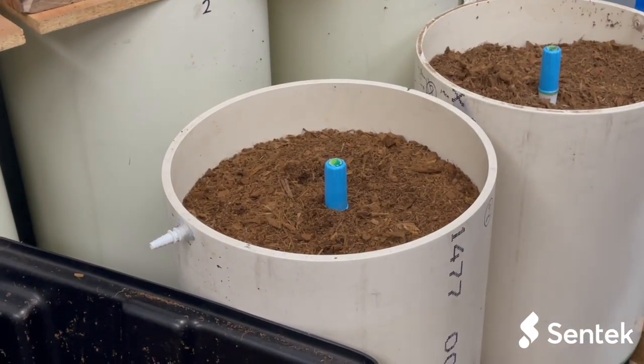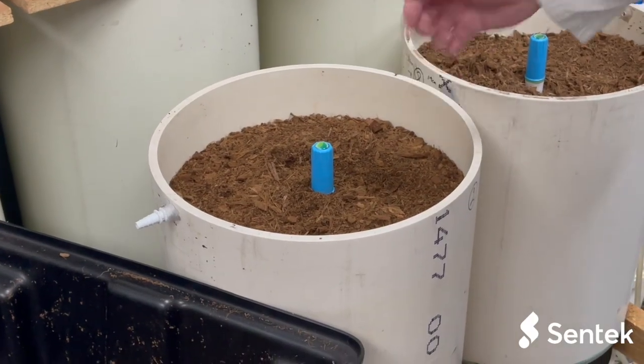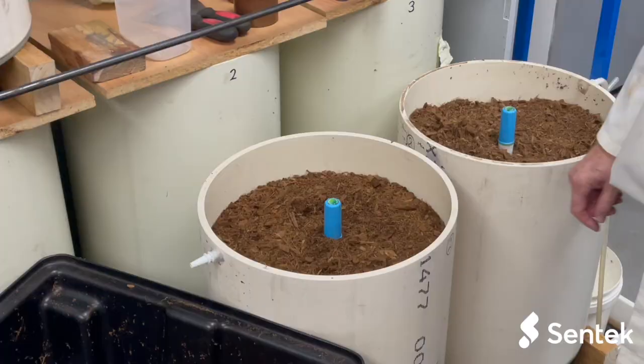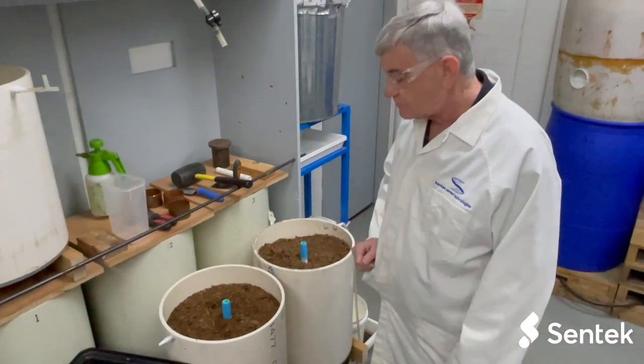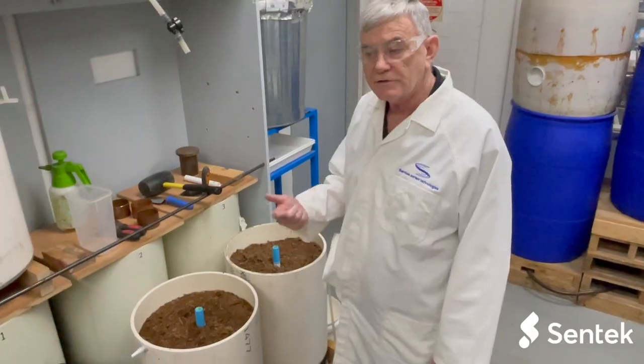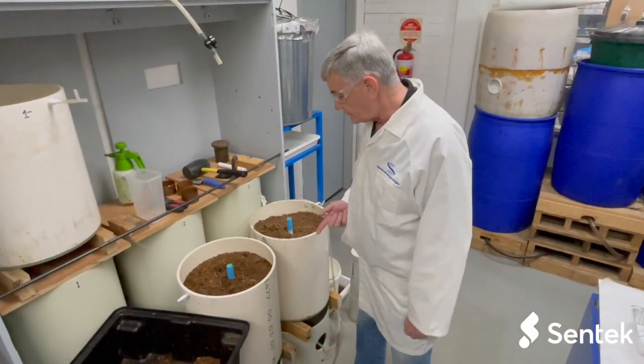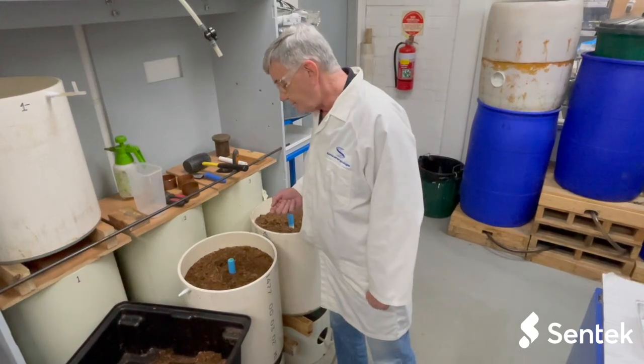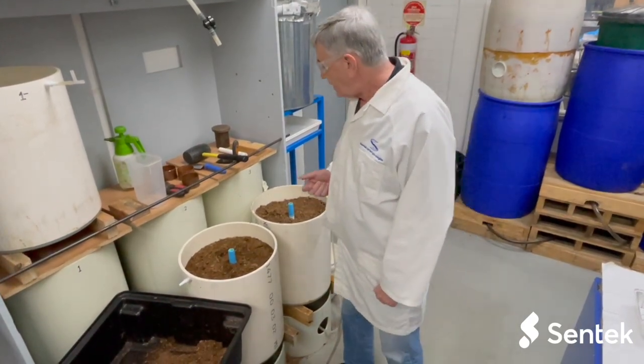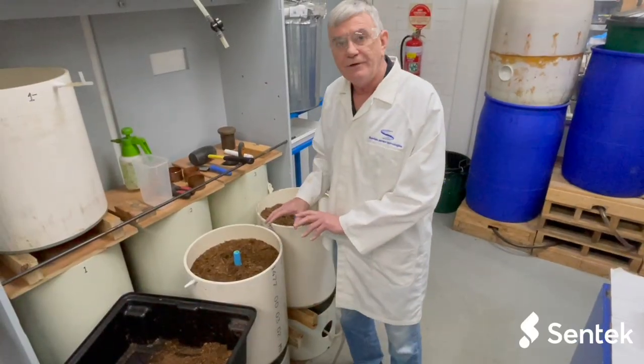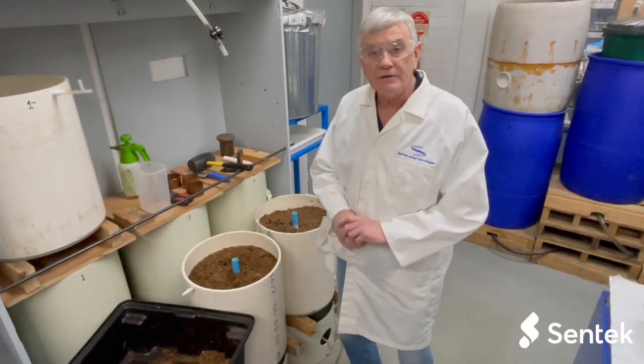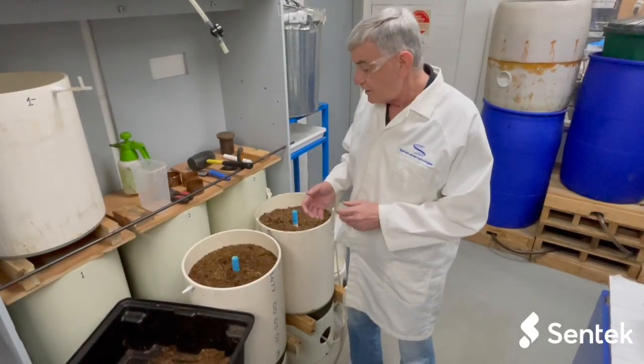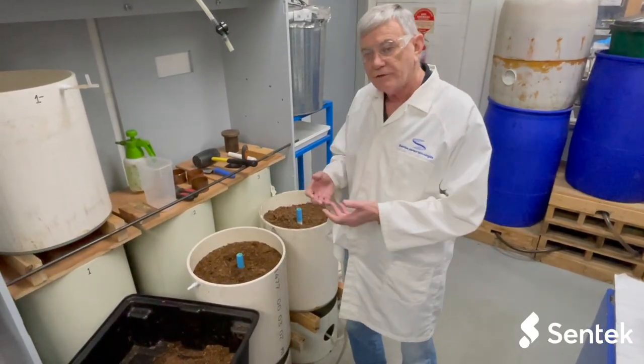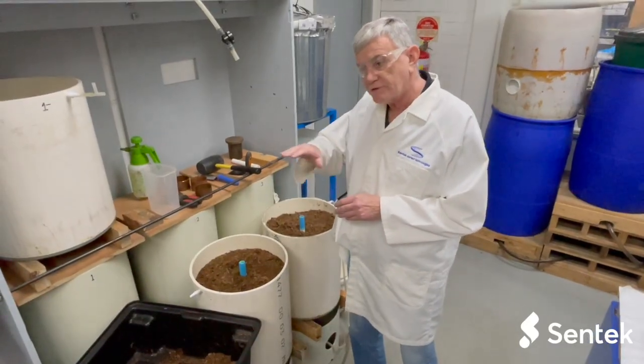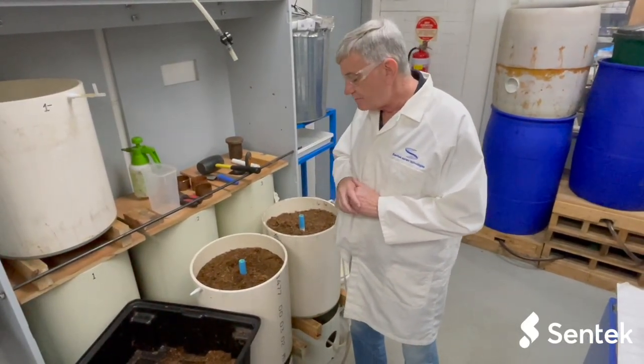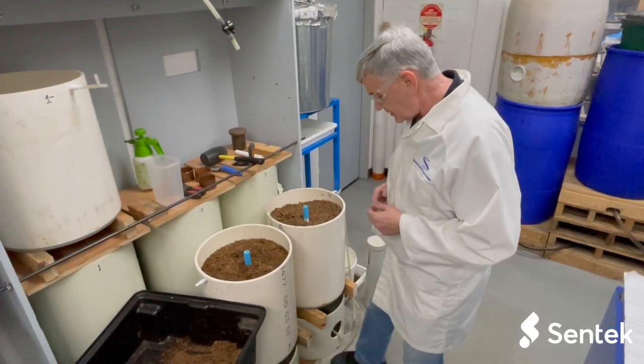Then I would check on the phone to make sure that I can speak to the single sensor and that I'm getting good values. Make sure that I've got the water content values, the salinity content, and the temperature. You need all of those values for the test to be valid. I would leave that for perhaps half an hour to let it settle. You do a download of the water content data and see if the signal is nice and flat. If it is, then you can start sampling.